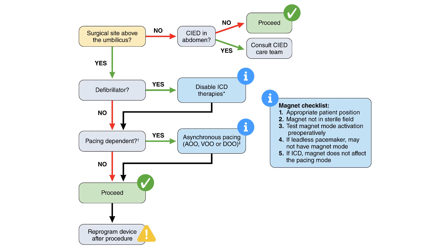We have a magnet checklist. If you're planning on using a magnet, then appropriate patient position during the procedure is important. Not all positions, such as prone, are compatible with using a magnet on the chest. The magnet has to be not in the sterile field. We want to make sure that the magnet mode activates preoperatively, especially in the case of leadless pacemakers, where it can be difficult to localize the device with the magnet. And some leadless pacemakers may not have a magnet mode. And if there is an ICD, then just a reminder that the magnet does not affect the pacing mode.